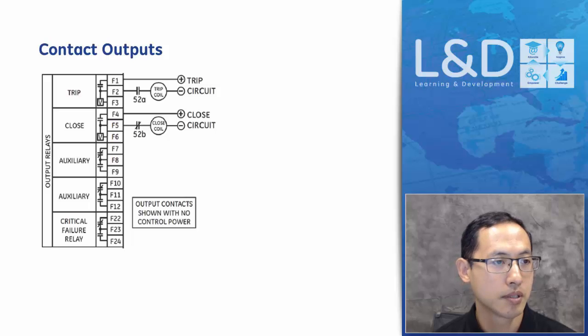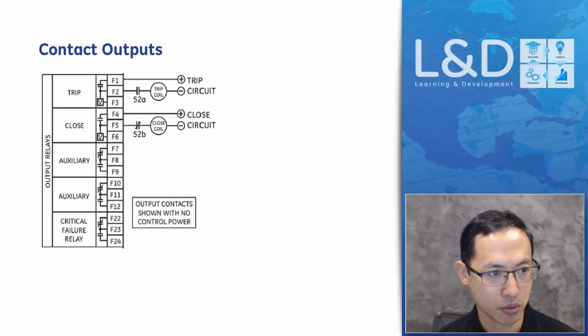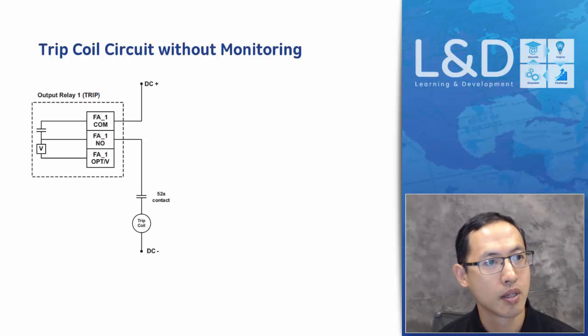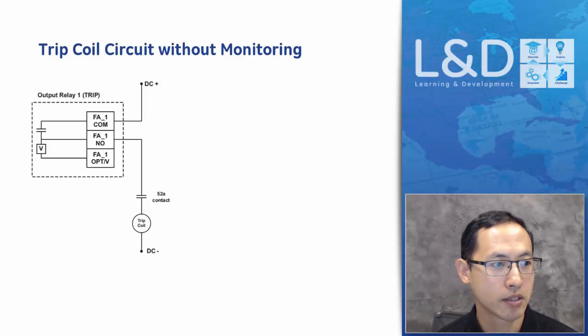For the contact outputs, each card has 5 relays, 2 form A and 3 form C, and the last one is a fail-safe relay, which means when the control power is removed, the relay will be asserted. And the form A contact has voltage monitoring, which can be used to monitor the trip coil healthy conditions. So here is the trip coil circuit. The first one has no voltage monitoring. Then the second one has monitoring with external jumpers.